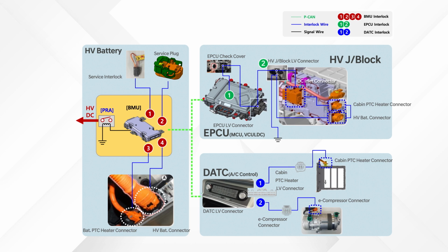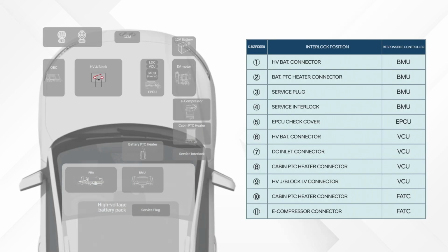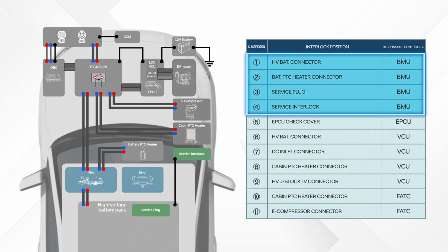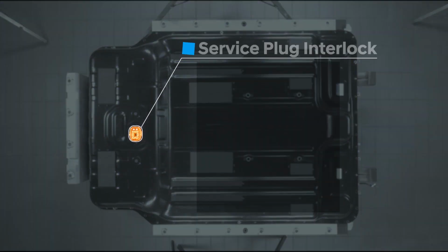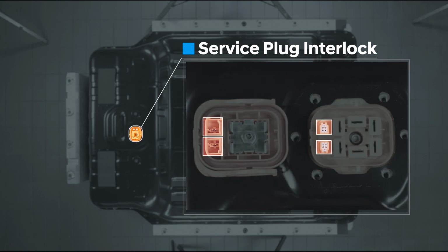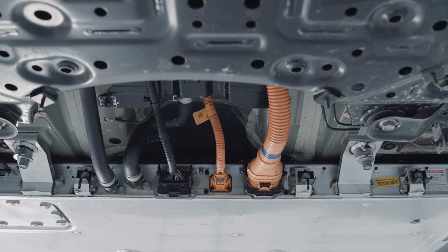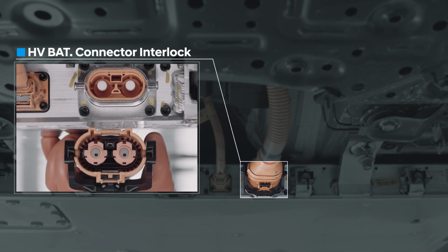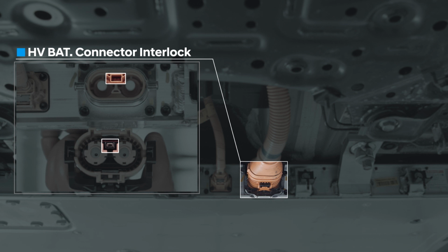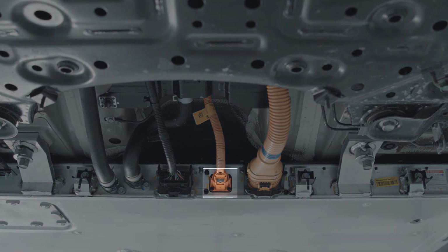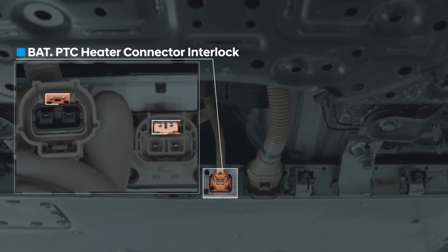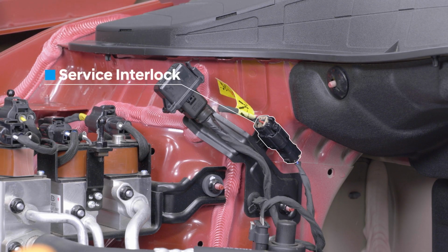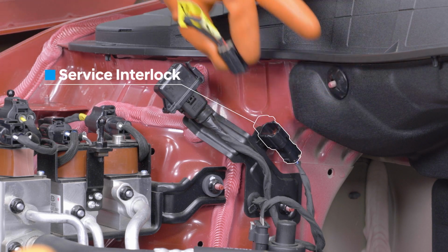Now, let's take a look at individual connectors connected to the interlock circuit. The first is 4 channels of interlock circuit detected by the BMU. Service plug, located on top of BSA. High voltage cable connector of BSA. Battery PTC heater connector of BSA. The service interlock located inside PE room.